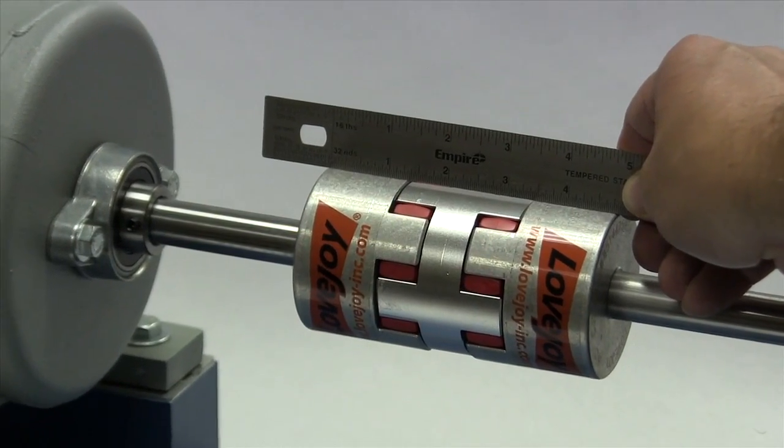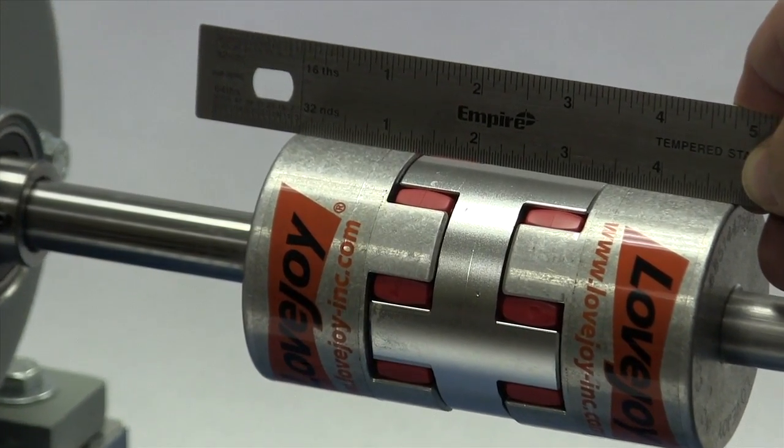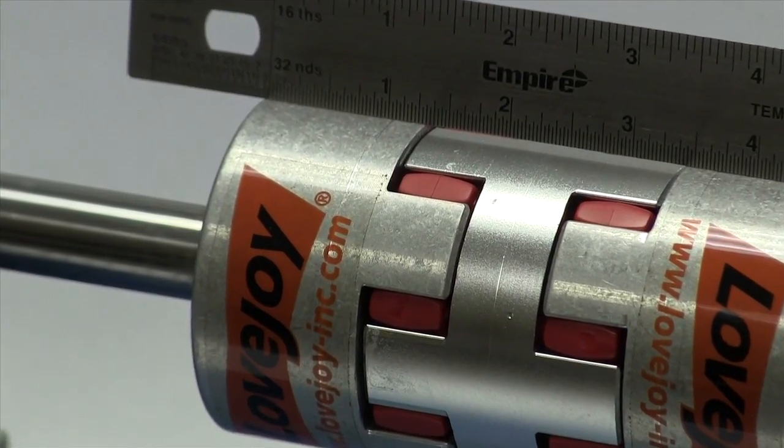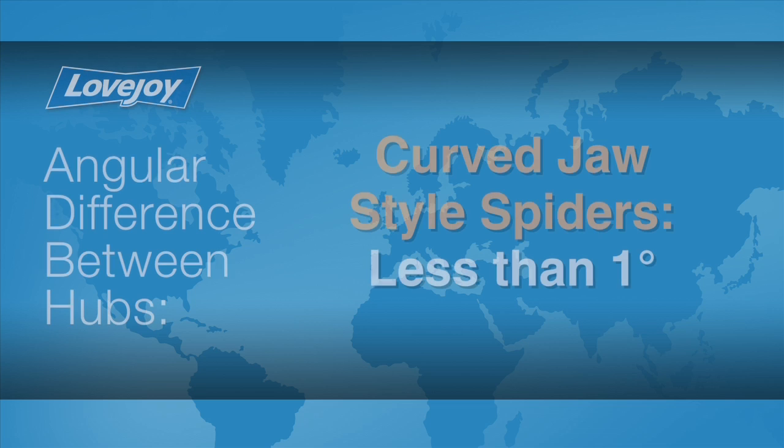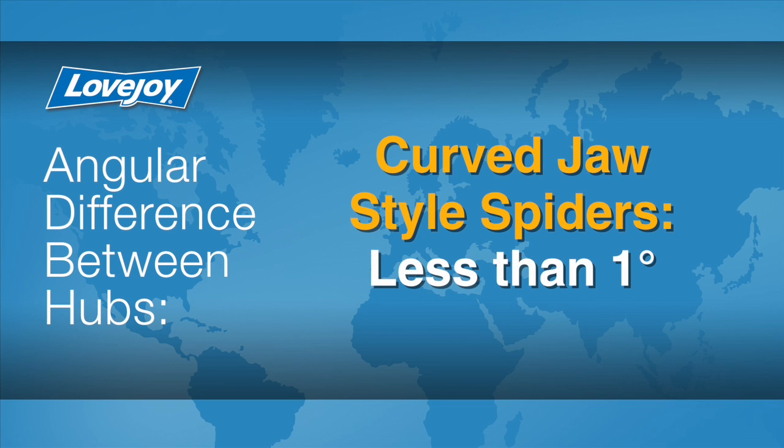The offset between the two hubs must be less than 1/32nd of an inch to prevent damage to the coupling. The angular difference between the two hubs should be less than 1 degree for curved jaw style spiders. If the alignment exceeds the allowable amount, realign the equipment to correct this condition.